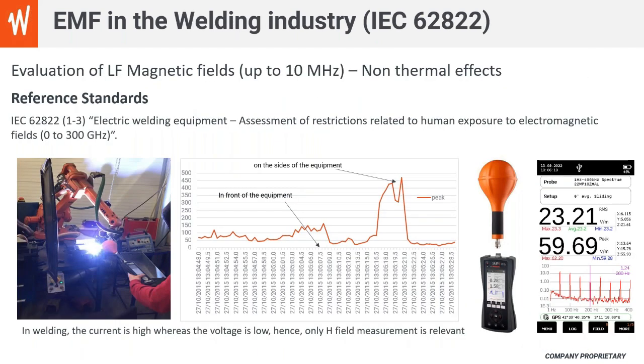The next application is also welding. Evaluation of low frequency magnetic fields up to 10 megahertz is required by the IEC standard, as there is a presence of very high currents which could lead to significant exposure to magnetic fields. So a portable instrument like the SMP3 is required to measure the welder's head, trunk, and limb exposure during active welding operations. So it's important to take into account the welding operation, and also the distance of the welder from the welding equipment before performing the assessment.